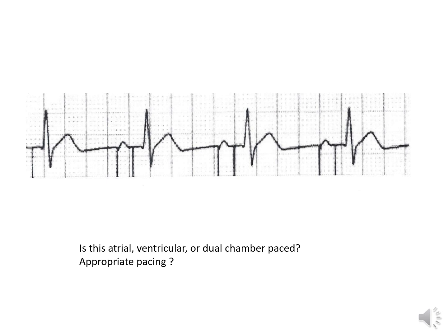This is a little trickier of a strip, and this strip has been passed around quite a bit with some of the pacemaker in-services we've had. But you see pacer spike, and there is a bit of a delay before the QRS. So technically that is not appropriate pacing. Technically you do have a failure to capture because the pacemaker spike is quite a far distance from the QRS.